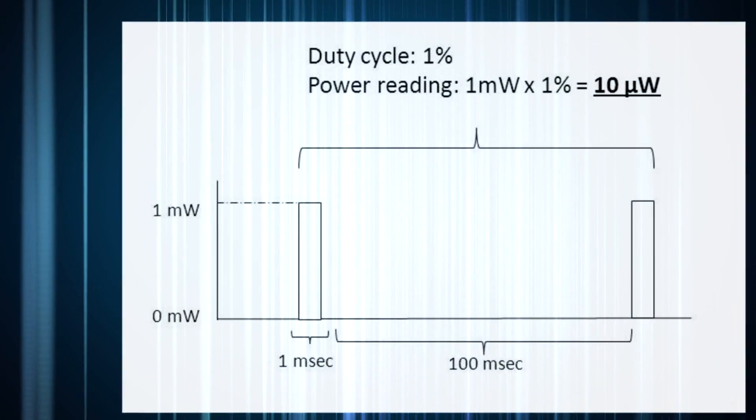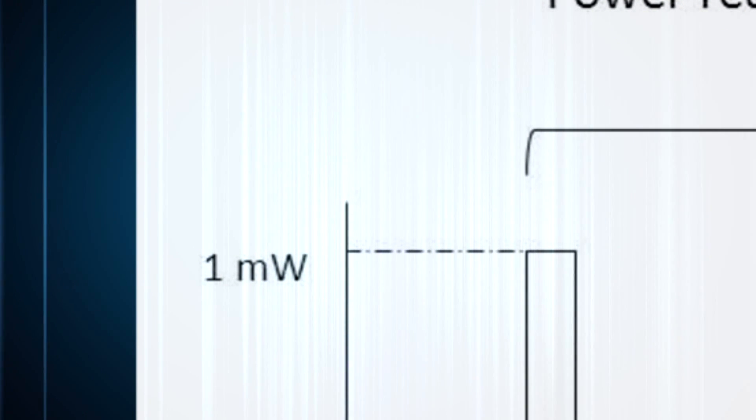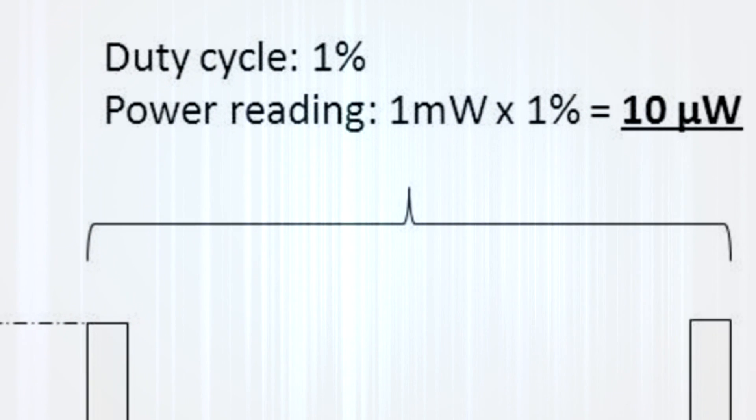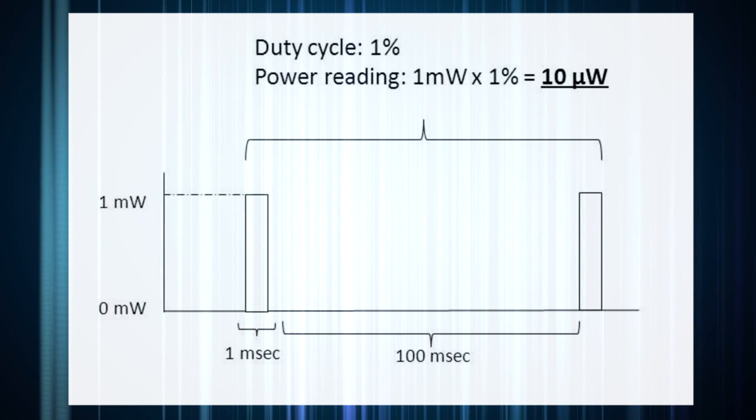Let's say we're trying to measure the power of a 1mW scanned beam with a standard photodiode power sensor, and the scan is such that the beam spends 1% of each cycle on the sensor. The average power reading of the sensor will be only 1% of the actual power in the beam.